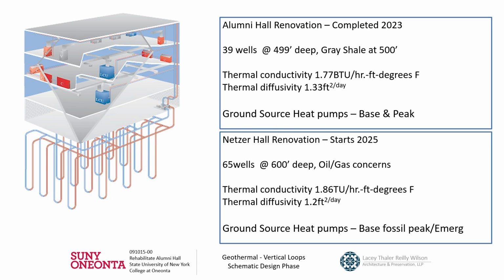So the difference is, on the second project, we're not going to have the building fully peak and base on geothermal. Firstly, there were space limitations with how much wells we could actually fit in the parking lot. And then we realized there's a lot of cost in doing additional wells when you already have the central heating plant connected to the building, and it's in excellent condition. There's a huge capital advantage to reducing the number of wells to more of a base load, or matching the cooling set to the cooling load.